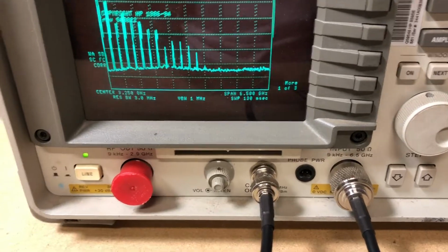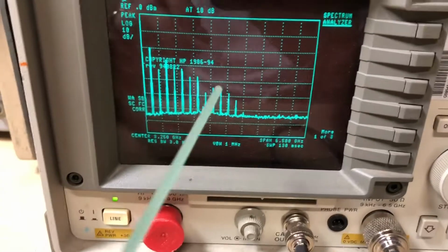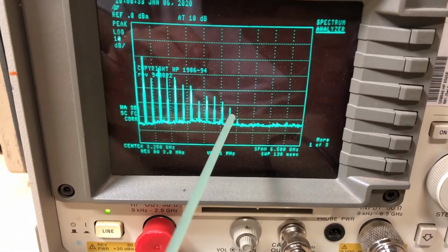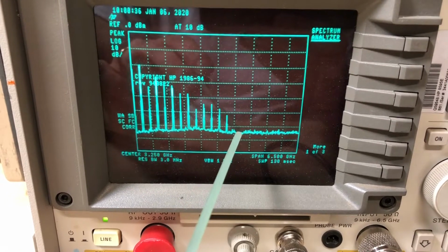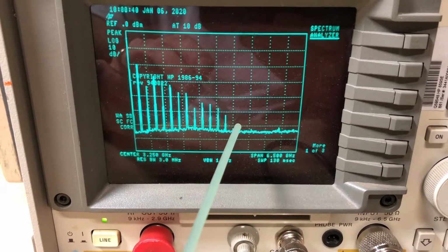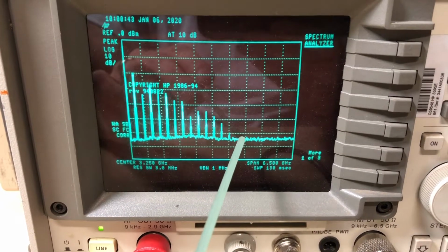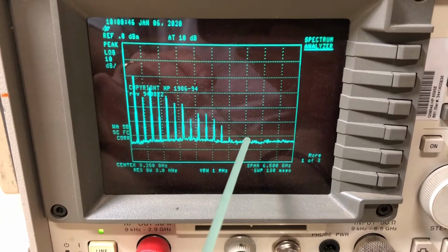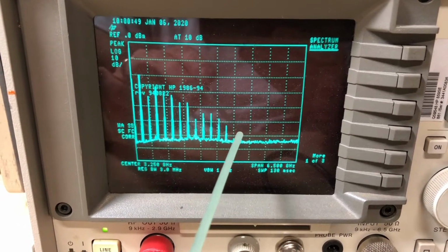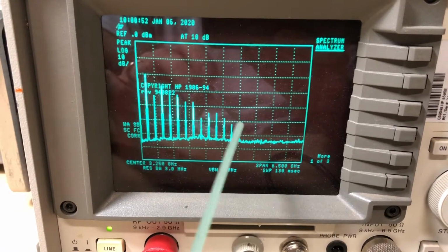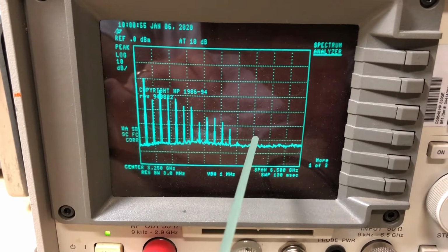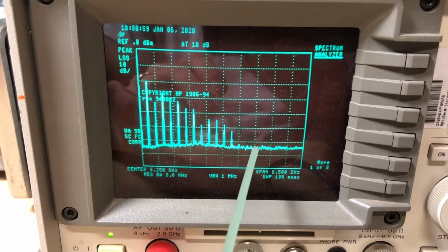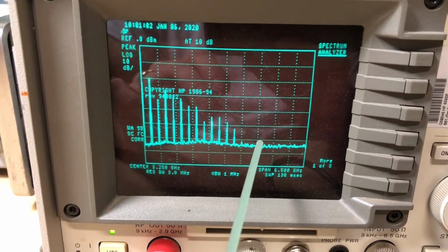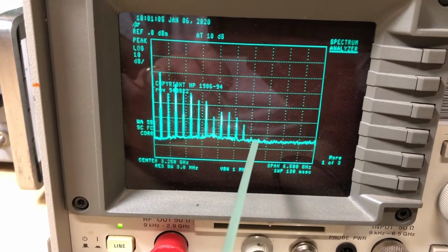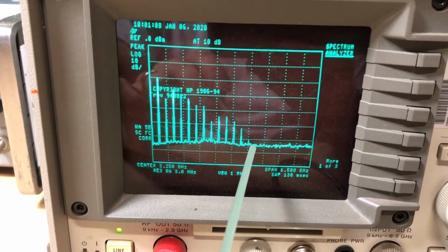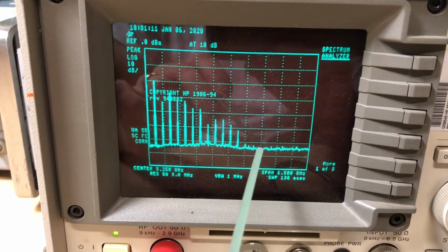These are all the harmonic spurs. But what happens here is so this is the 3.6 gigahertz spur. The next spur should be 3.9 gigahertz, and there should be one more at 4.2 gigahertz. The spurs should, from what I've seen on other analyzers, extend out to this graticule line here, all the way out to here, at least 4.2 gigahertz. And you can barely see there's a spur right there, and then there's nothing after that.